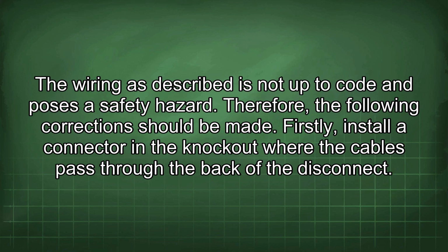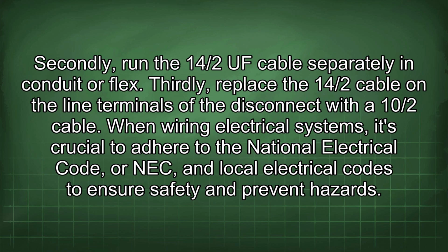Firstly, install a connector in the knockout where the cables pass through the back of the disconnect. Secondly, run the 14/2 UF cable separately in conduit or flex. Thirdly, replace the 14/2 cable on the line terminals of the disconnect with the 10/2 cable.